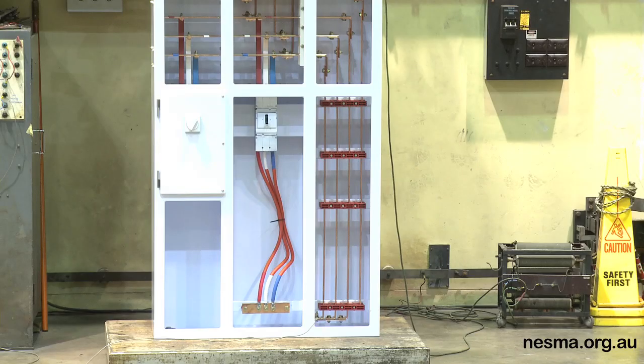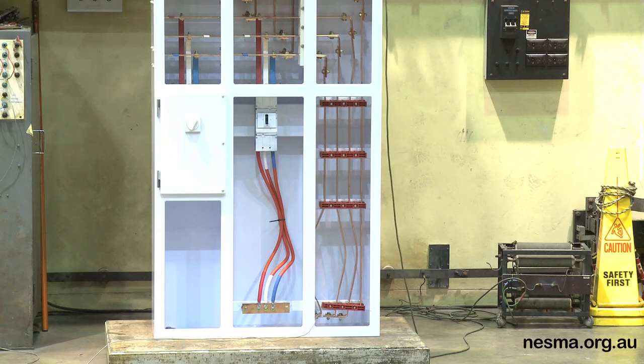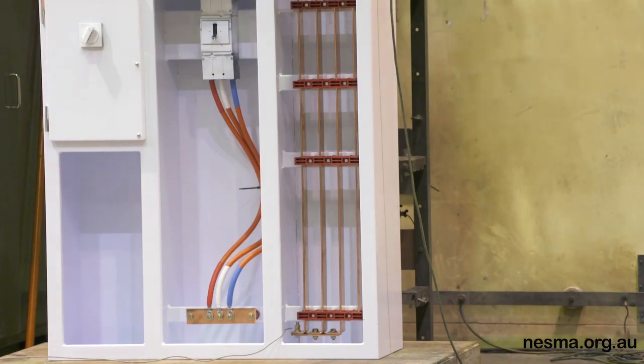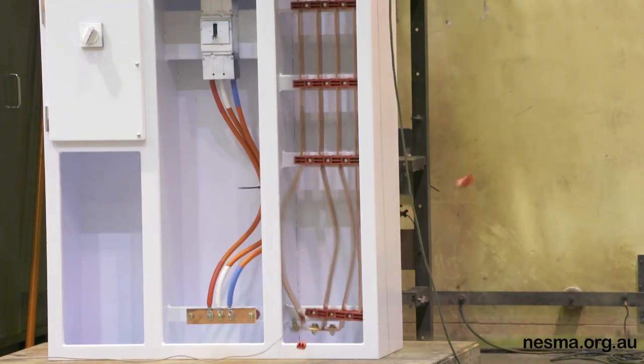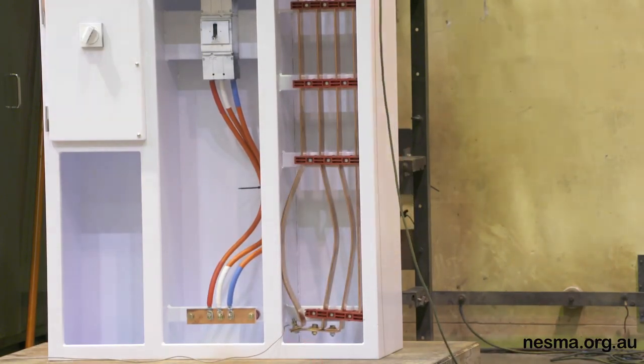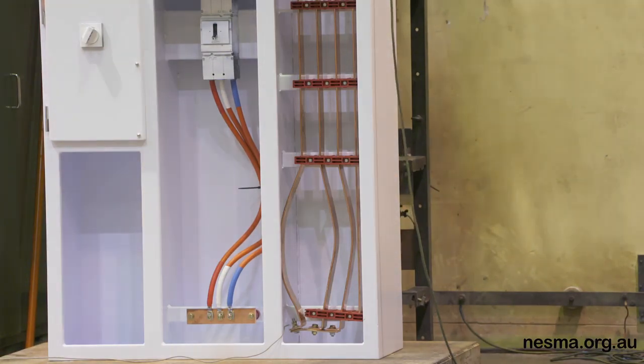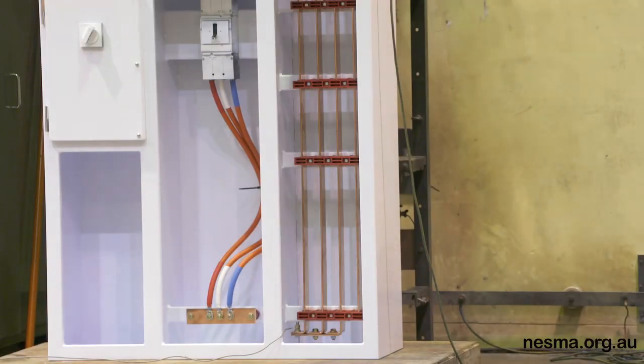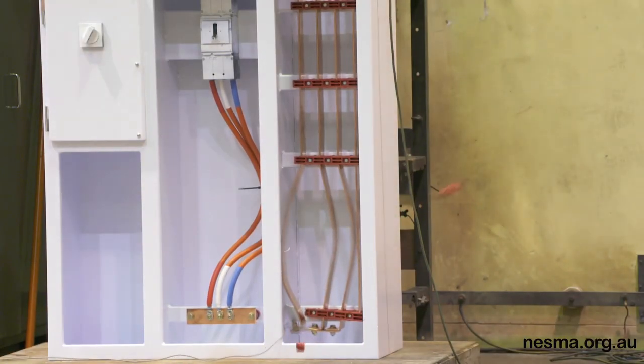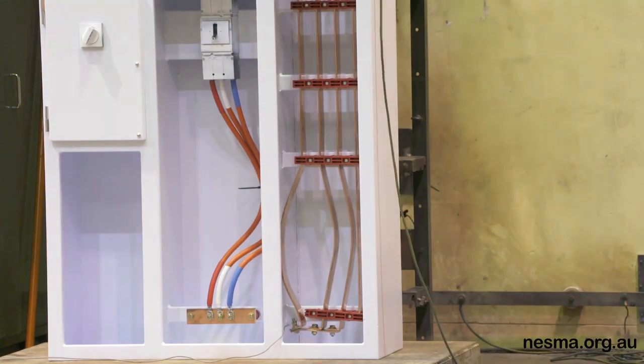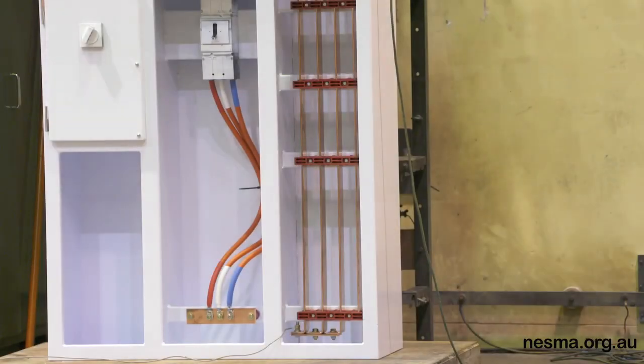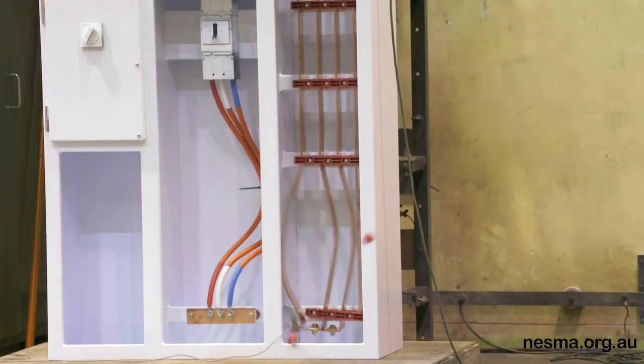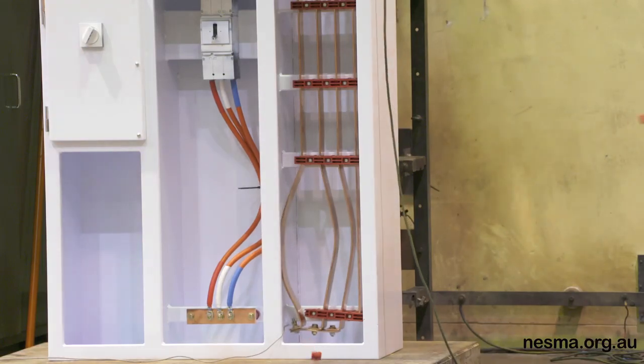So what you can see is the bus bar on that far left-hand side was repelled from the other two, and what we've got is the current. You're seeing a bit of vibration in the bars, and that's as the phase rotation of current is occurring during the test. We do see, even though the vertical bus bar system is supported at the very base by the bolted short circuit, it broke the bottom bus bar support because there was so much deformation.